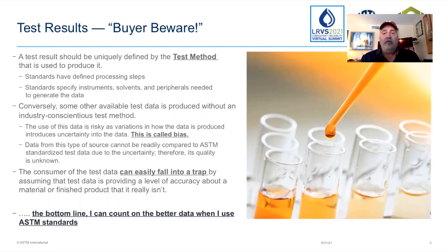But the problem is that when we get data, it's important that it be accurate, but also important that we understand what that accuracy is. We could fool ourselves into making poor decisions. For example, if it's data that is a plus or minus 10 or 20 or 30 ppm, we could see a trend in the data that really isn't there, because any number within that range is essentially statistically the same number. So we could overreact, or we could underreact. We could miss a problem, or we could make a recommendation to the plant when absolutely nothing is wrong. Both of those cases can be very, very difficult to recover from.